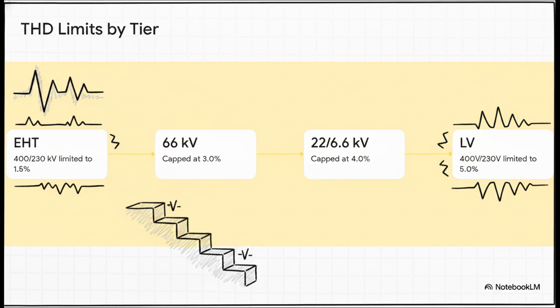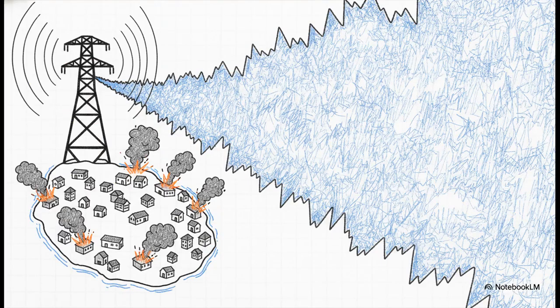Now let's move on to total harmonic distortion, or THD. This actually follows a descending staircase. It's strictly capped at extra high voltage at just 1.5%, and the limit actually gets looser as the voltage drops, all the way down to 5.0% at low voltage. Now, that might seem a bit counterintuitive, right? Strictest at the top, but distortion is capped strictest at extra high voltage for a really good reason. That is exactly where dirty waveforms can propagate the furthest and cause the most widespread damage across the entire grid.